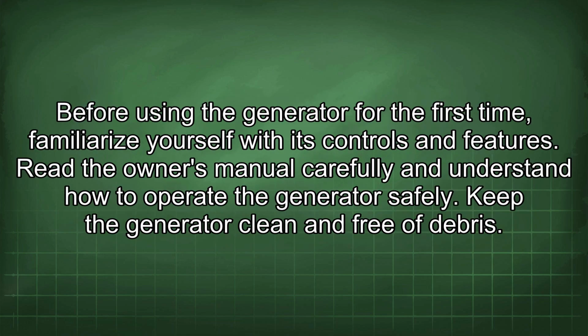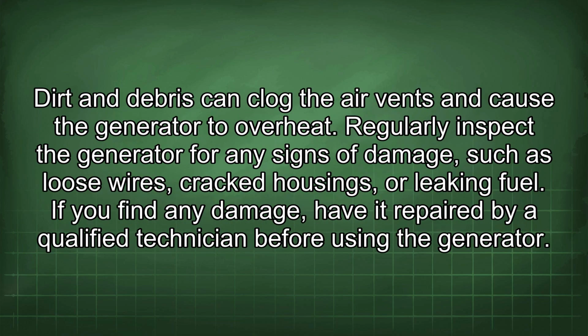Before using the generator for the first time, familiarize yourself with its controls and features. Read the owner's manual carefully and understand how to operate the generator safely. Keep the generator clean and free of debris. Dirt and debris can clog the air vents and cause the generator to overheat. Regularly inspect the generator for any signs of damage, such as loose wires, cracked housings, or leaking fuel. If you find any damage, have it repaired by a qualified technician before using the generator.